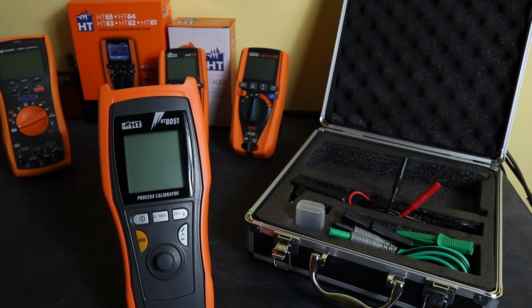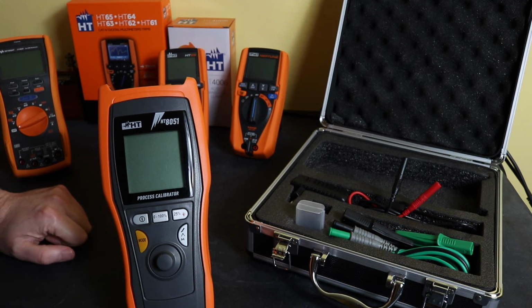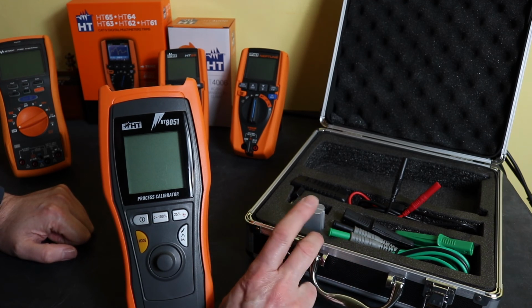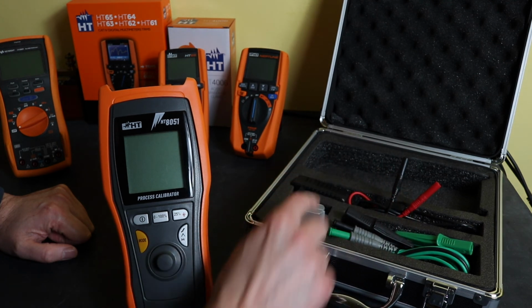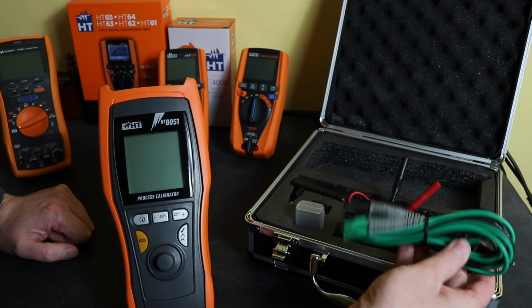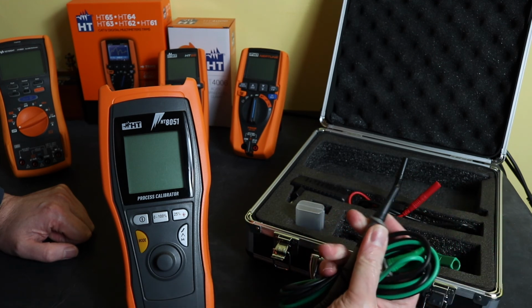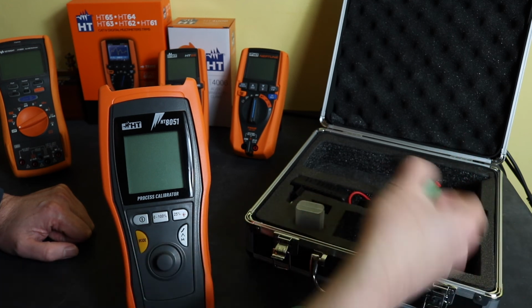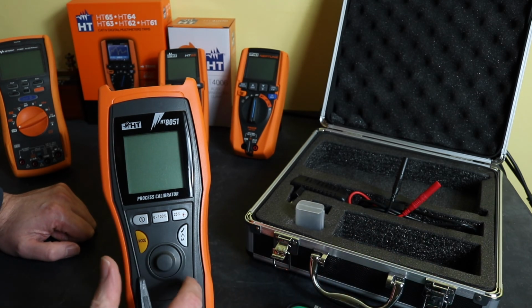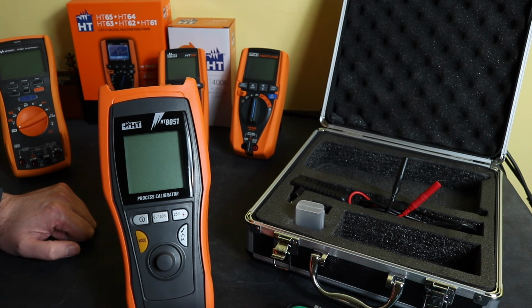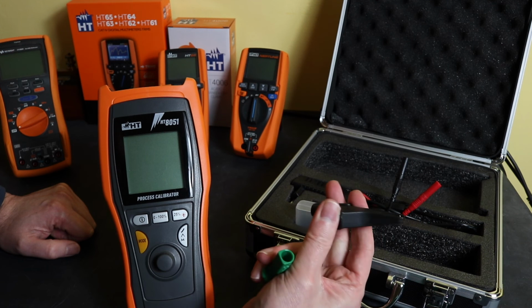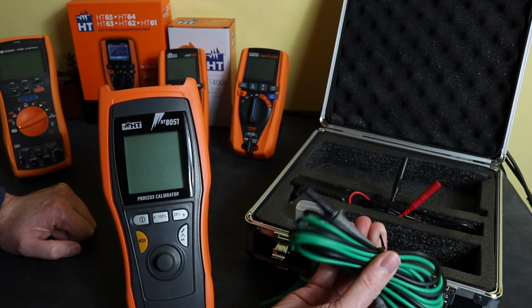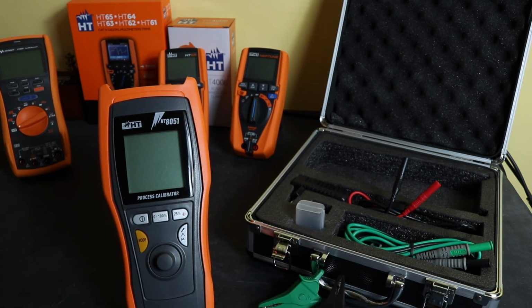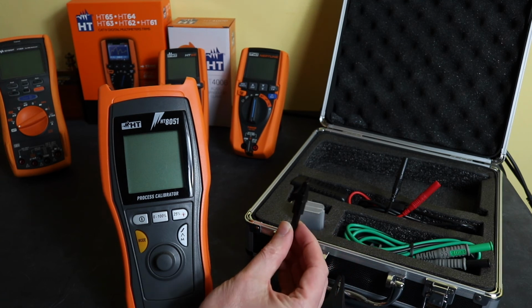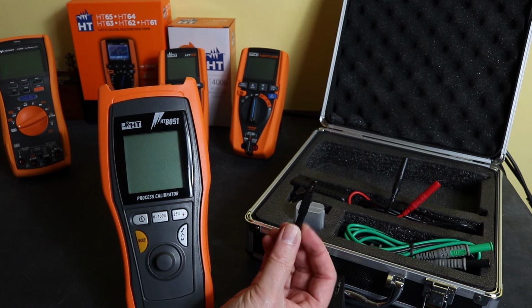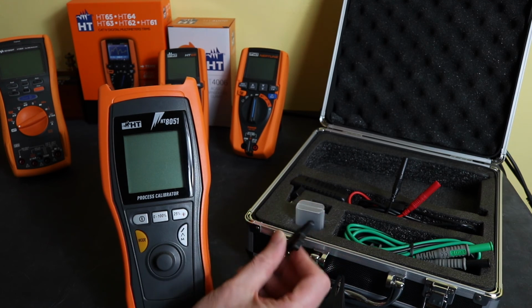So just before we bring the video to a close, let's go through the meter itself. As you can see, it comes in this kind of flight case arrangement. This was the holder for the battery that it came with. Pocket at the front here, you've got the leads, two leads with it that come with probes attached to them, and then a crocodile clip for each one. To my mind, given that this is for actual transducers and fairly small wiring systems, I would find these crocodile clips a little bit too big really, and the probes as well. For getting into terminals, they're probably going to be too big as well. I would probably favour for work on transducers and clipping onto those, this style of crocodile clip, much smaller, will get much better grip on the wiring than these two will.